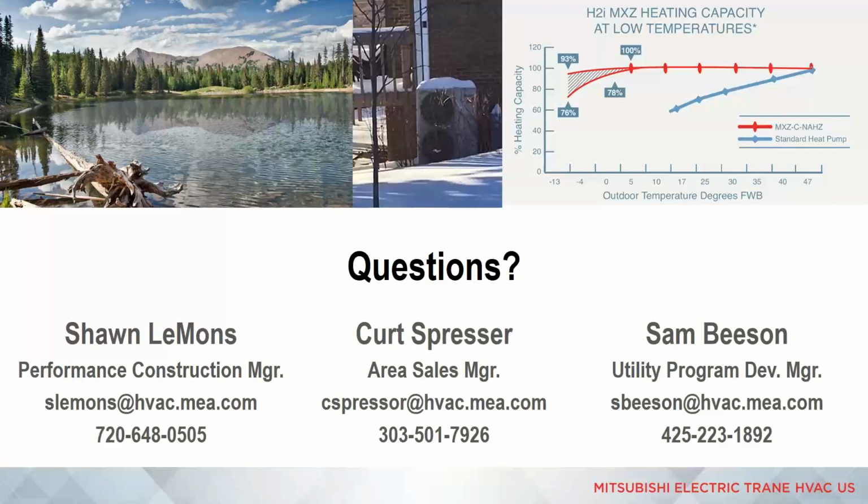And there's some barriers to that, though. R32 is slightly flammable, and so at present we don't have building standards that will allow us to use that inside a building. So those things are being worked on now, and at the federal level, we'll see some pretty big changes as we approach the 2023, 2025 timeframe. And as manufacturers, I just want to let everybody know that we're fully in the loop on that. We're prepared for it. We're actually using R32 in Europe and have been for a couple of years on the residential side and transitioning to that on our commercial products in Europe now. So it's a great question.